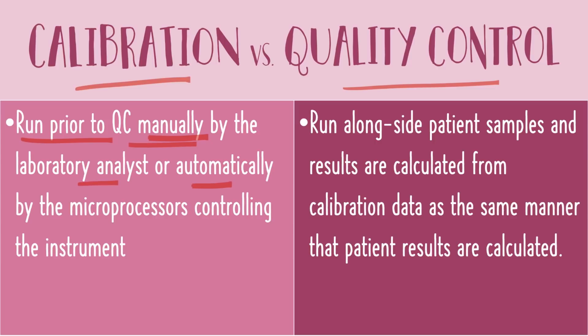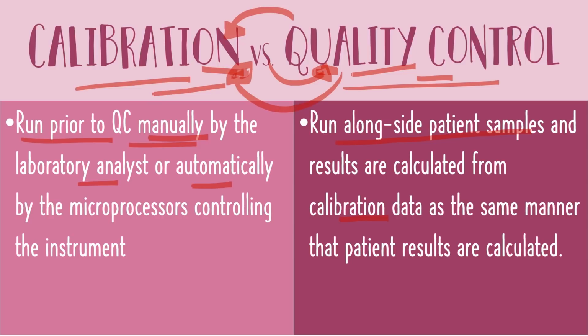So when do we need to do calibration of our procedure or our instruments? Okay, so that is based on the quality control results. So your quality control samples can be run alongside patient samples, in which the results are calculated from the calibration data. So therefore, the results of your quality control samples are going to be dependent on the manner of calibrating your machine. So therefore, if may problem sa calibration, this will always give out erroneous quality control results. So therefore, merong error na nangyari. So the evidence for using calibration should come from QC sample results. So mainly, quality control is actually going to evaluate the type of calibration that was done on your machine.